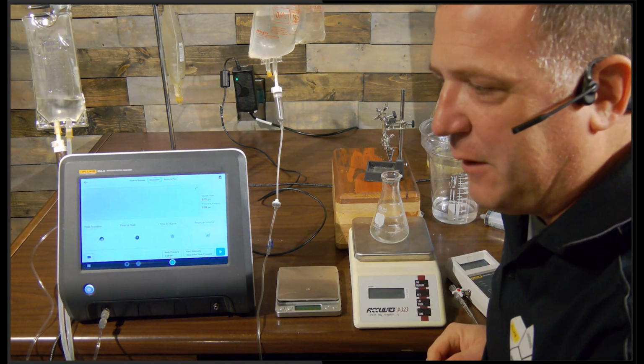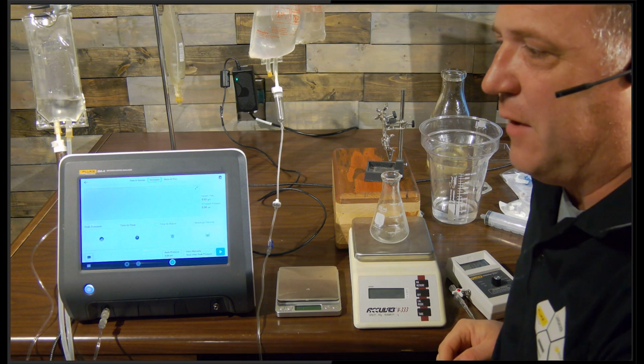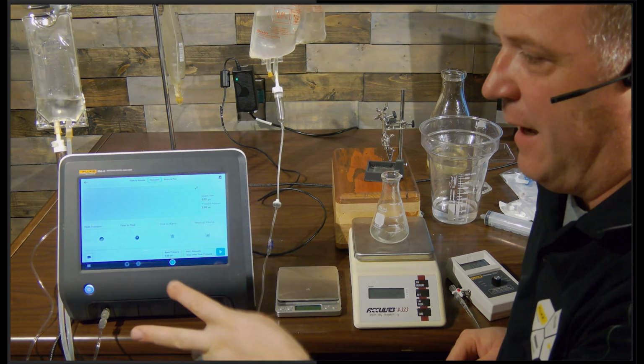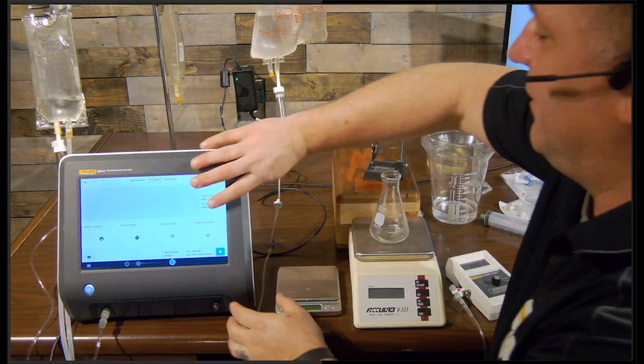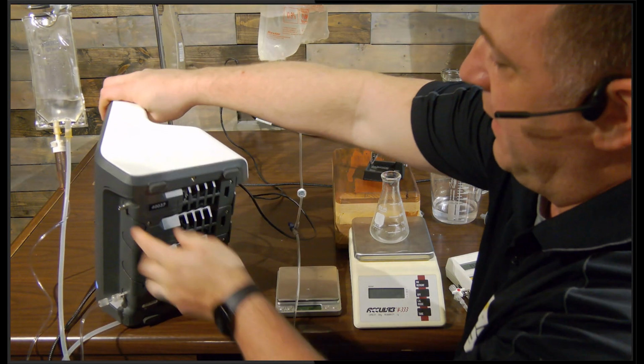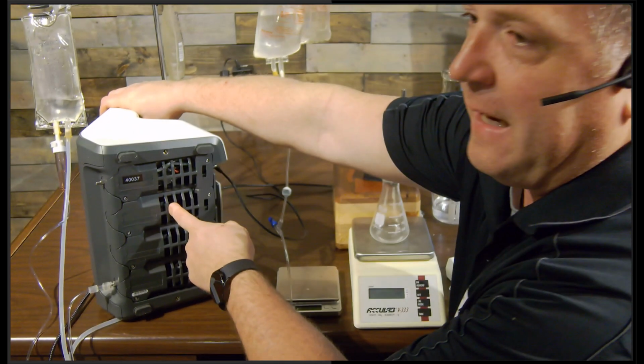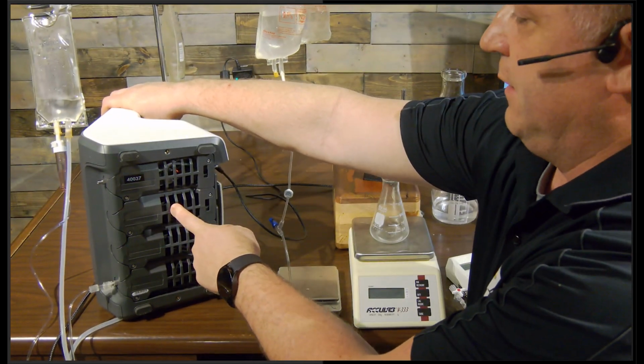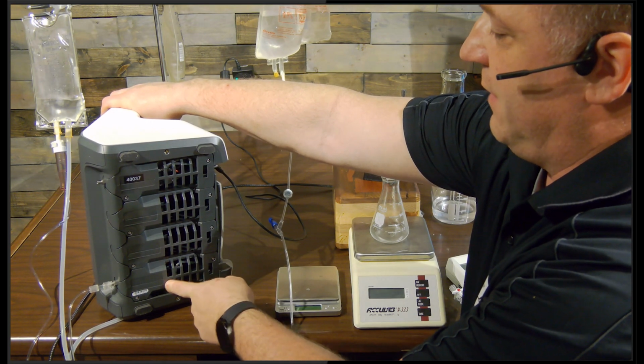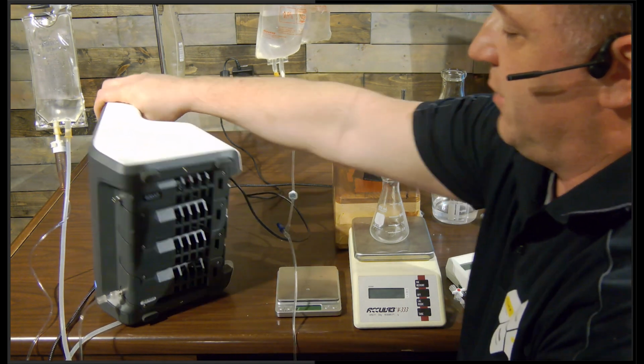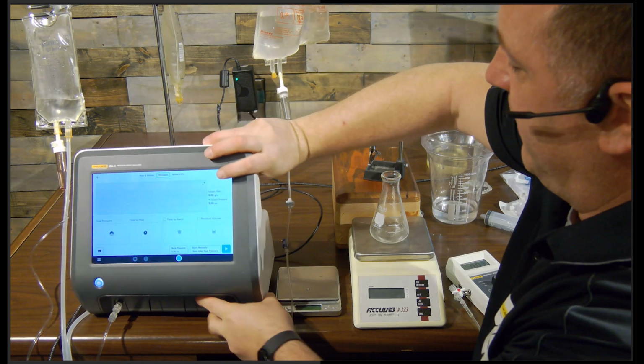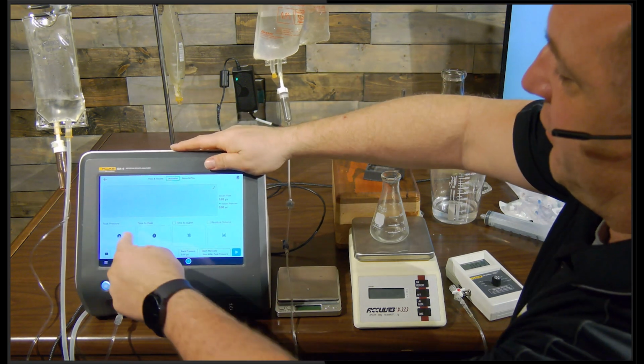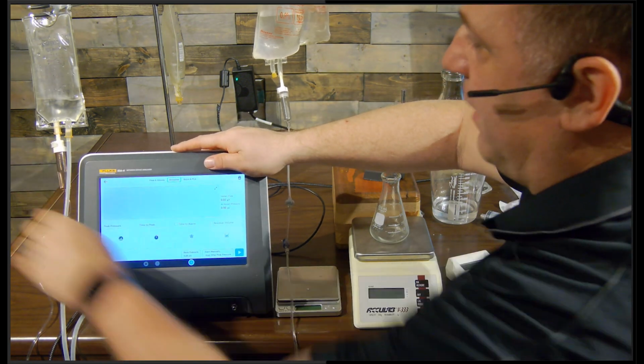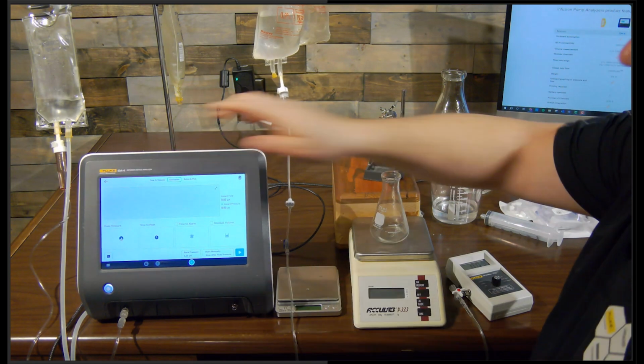Another great question. For the people who want to set up and run 2 pumps at a time, a feature about this IDA-6 is I can simply flip this over, and I can take out these two blanks, and I can add two more channels to it. So if I started off with a 2-channel IDA-6, I can add two more and turn this into a 4-channel IDA-6. And in which case, maybe I choose channel 1 and channel 2 for one pump, and channel 3 and channel 4 for the second pump.